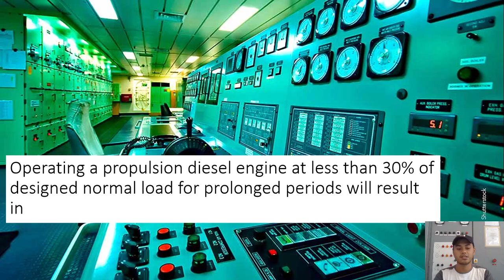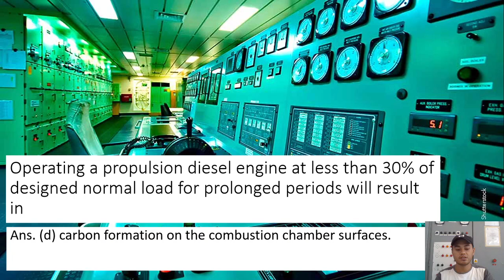So when an engine is operated at such low loads, the turbocharger efficiency drops. When the turbocharger efficiency drops, less quantity of air is supplied to the cylinder. Hence, the quantity of air available in the cylinder for combustion is reduced. This will automatically reduce the quantity of fuel which is burnt. At the same time, the fuel will not burn efficiently. Thus, unburned fuel will lead to carbon formation and the combustion chamber surfaces will get coated with carbon deposits.